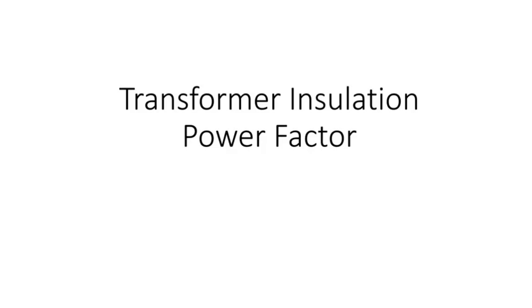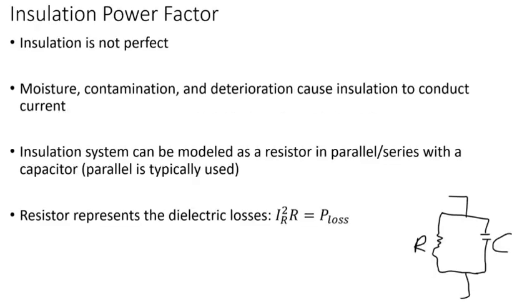In this short video, I'll talk about transformer insulation power factor. This test is really critical. Why? We know inside the transformer there is a lot of insulation: paper, pressboard, wood, oil. Insulation is not perfect.